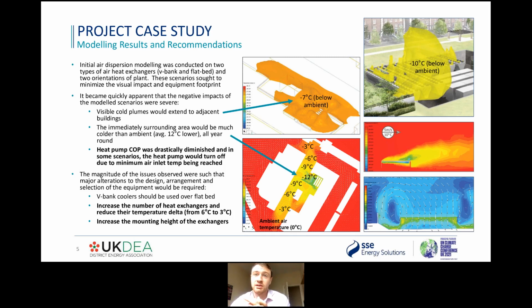The worst impact that we saw was the heat pump COP. It was drastically diminished, so much so that, as we had alluded to earlier, the heat pumps actually turned off due to the minimum air inlet temperature being reached, or we simulated that the heat pumps would turn off. So the net result is that this solution wasn't technically viable in any way. So we went back to the drawing board because the magnitude of these issues was so severe.